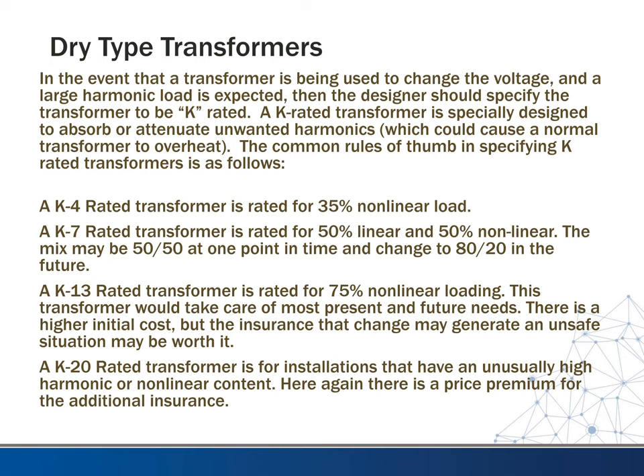In the event that a transformer is being used to change the voltage and large harmonic loads are expected, then the designer should specify the transformer to be K-rated. So a K-rated transformer is specially designed to absorb or attenuate unwanted harmonics, which could cause a normal transformer to overheat. So the common rules of thumb in specifying K-rated transformers are as follows.